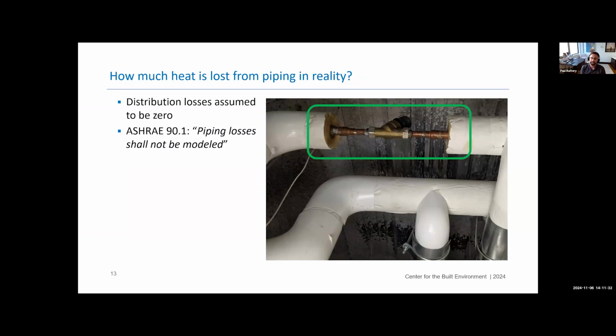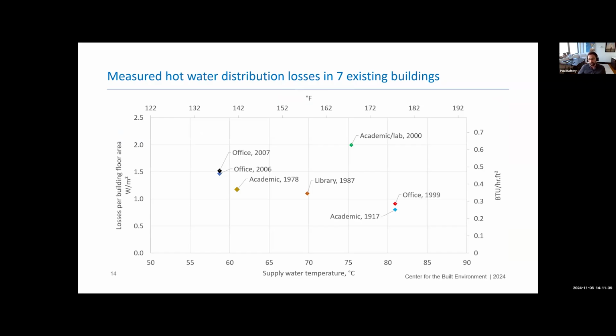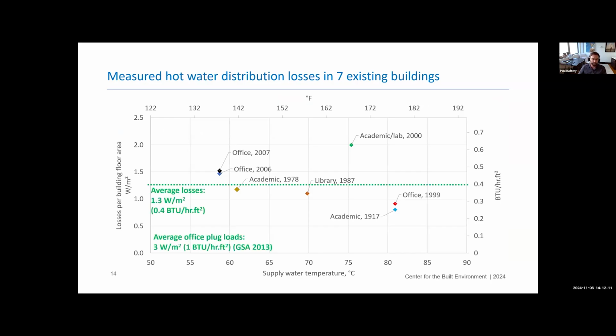So what we wanted to do is go out and actually measure these losses. And what you're seeing here is the supply water temperature of the hot water system on the x-axis, and then the actual losses normalized against the building floor area on the y-axis. And these are 7 different buildings where we went in and took these measurements. Essentially, we turned off the air handler, closed all of the valves to radiators or fan coils or VAV boxes, and just circulated hot water in the system and measured how much energy it took to keep that system at the normal temperature and flow that it operated at. And for some context, the average of these losses is just a little bit less than half of average plug loads in office buildings.